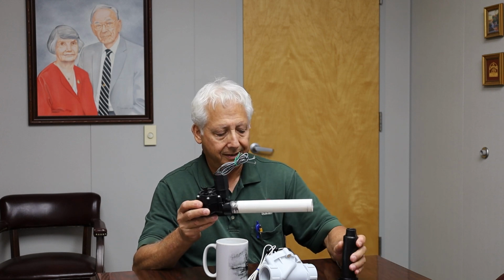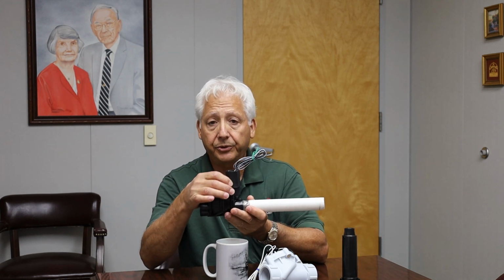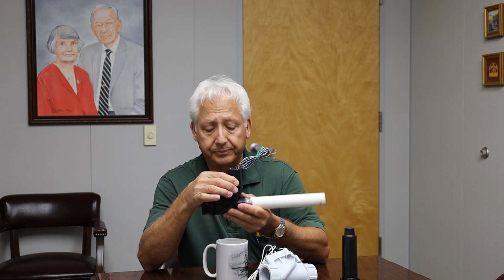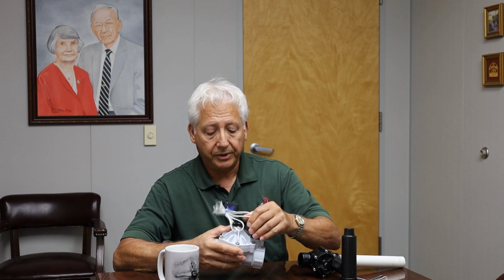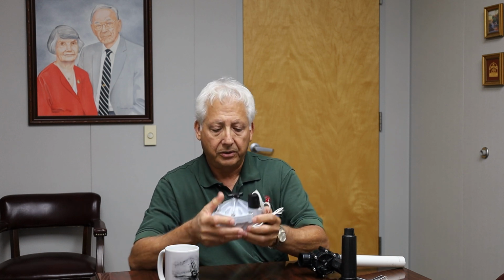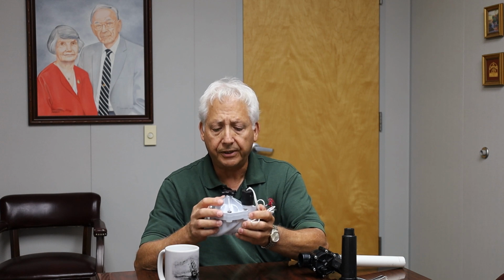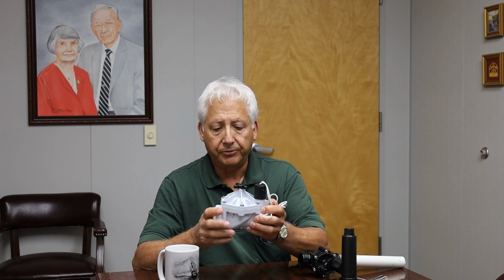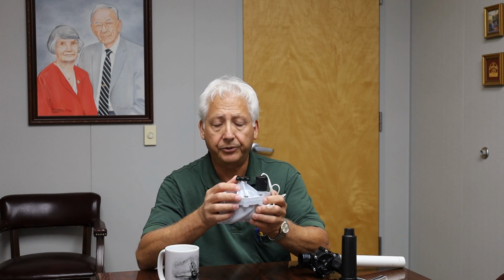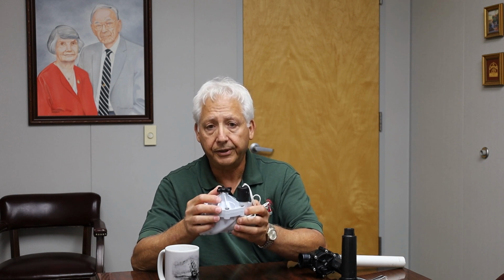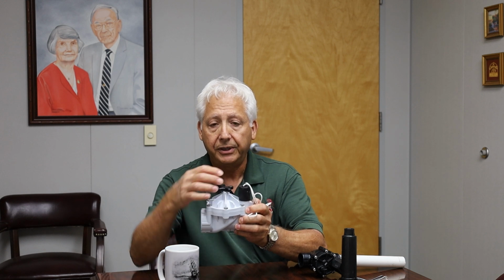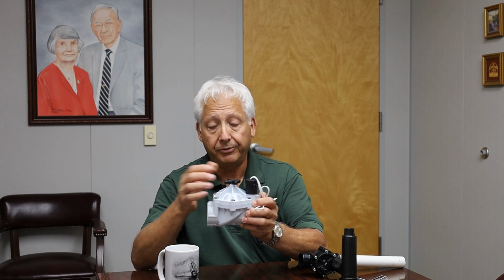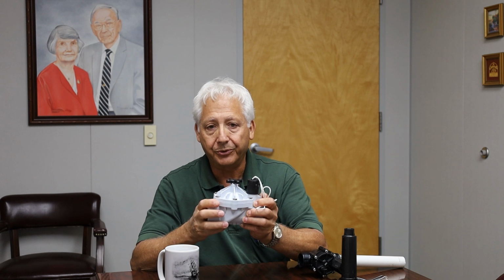Now, if a valve doesn't open at all, we can assume that it is the solenoid. The solenoid could be shorted out. Or, if the valve is so equipped, we could have a valve with a flow control. Now, the flow control comes in handy because it allows the user to control the amount of water downstream, but also if the valve fails, you can turn the flow control off. If you forget that it's off, of course the zone won't work.